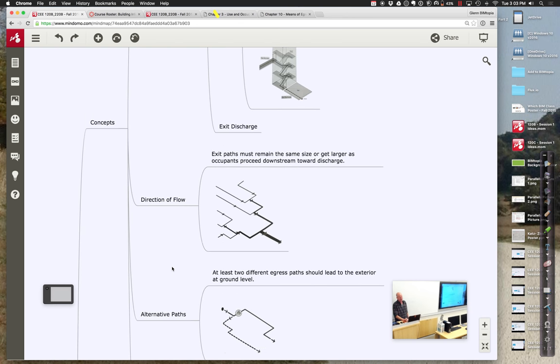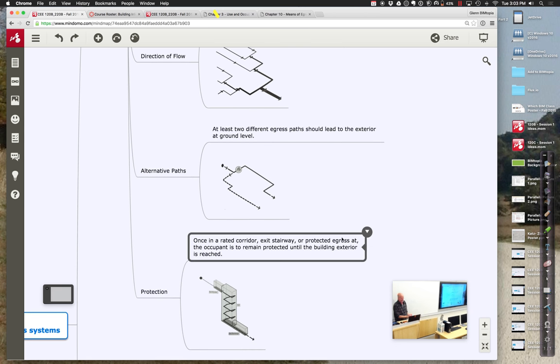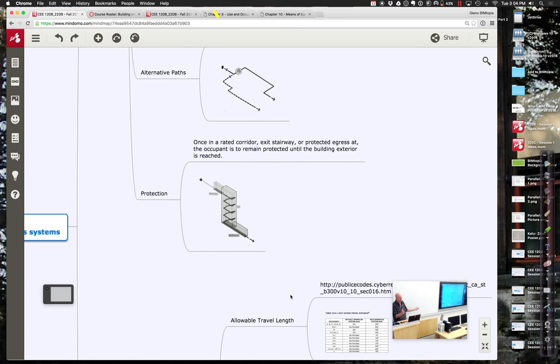An important concept is the direction of flow — as you move from the most remote spot outward, things tend to get larger because more and more people aggregate, and you don't want bottlenecks. Another key concept is alternative paths: at any one spot you'd like two options, because if there's a fire along one path you're trapped. It's nice to have branching so you can go several different places. Also, once you're in a protected zone, you must remain protected — I can't take you from a safe zone to a less safe zone.